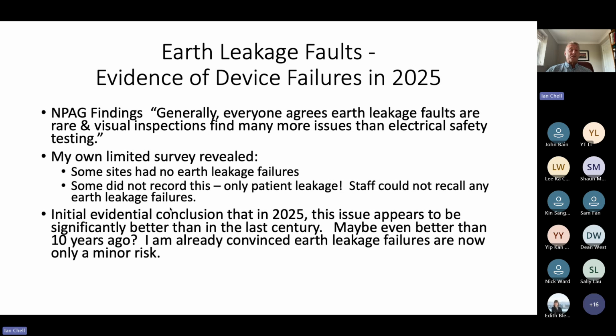I actually found out that some sites didn't record this, only patient leakage, but the staff could not recall any earth leakage failures, even though they were testing them. It's just that it's not been recorded. Okay, so that does need to improve, I think. Some sites had no devices that had suffered earth leakage failures. So there you go. That's the evidence.